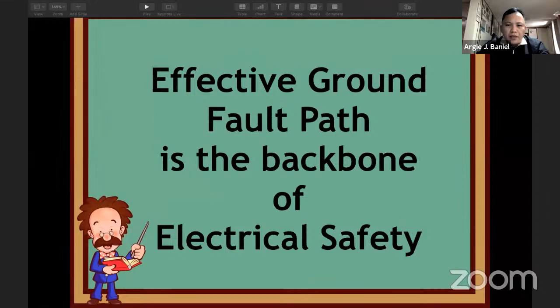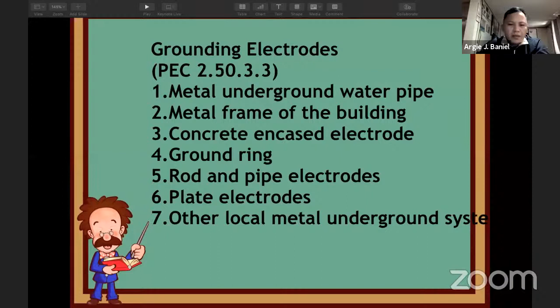Among the grounding electrodes, especially number 1, the metal underground water pipe, the metal frame of the building, concrete-encased electrode, the ground ring, the rod and pipe electrodes, the plate electrodes, and other local metal underground systems.